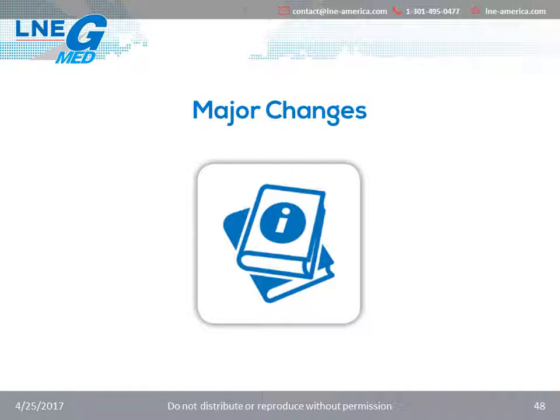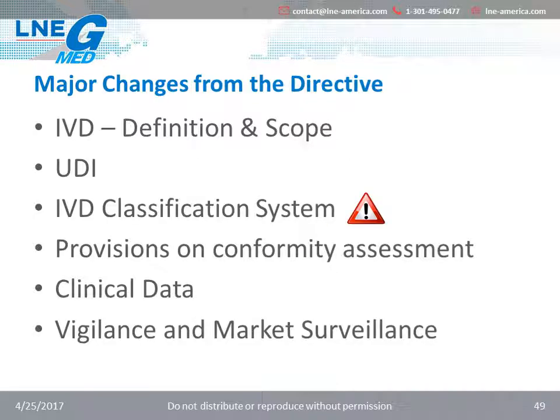So the major changes from the directive to the regulation include the definition and scope of IVD. There is a much wider and broader scope. The UDI, or Unique Device Identification System. There's a new classification system for devices. There are new provisions on conformity assessment. There are also new requirements for clinical data and much more prescriptive requirements for vigilance and market surveillance.